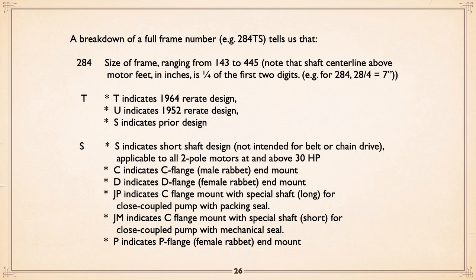The S, as in 284 TS, the S at the tail end, indicates, as I mentioned before, a short shaft design, not intended for belt or chain drive, applicable to all two-pole motors at and above 30 horse. Below that, they don't throw in the S, but if you get it at and above 30 horse, then they do.